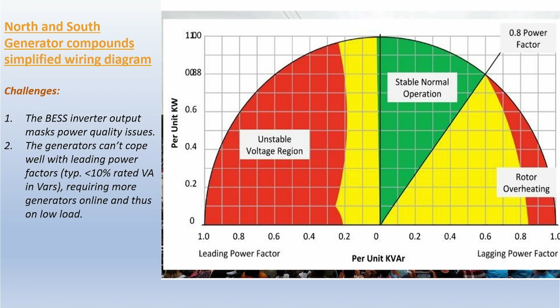Without boring you with the maths, there's a very basic graph of power factor operation on generators. Lagging power factors, where the generator engine has to work harder to turn the alternator, you can cope with quite readily, and that's the nice big green region. But if you look at the black line, you just get a very thin whisker of green on the left, which is the leading power factor. Most switch mode power supplies are slightly capacitive, and that capacitance creates a leading power factor, which causes the alternator to accelerate, and the generators can't cope with that. So there's a very, very thin window where they can run with leading power factors before they become unstable and turn off. That was our first challenge we had to overcome.